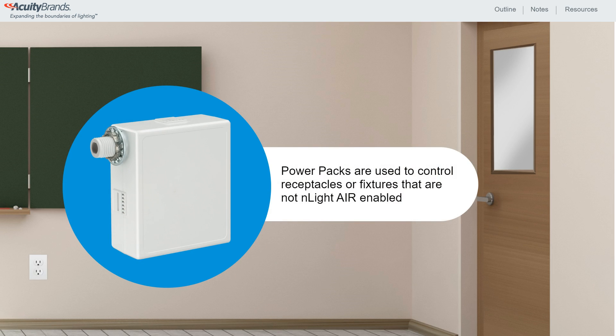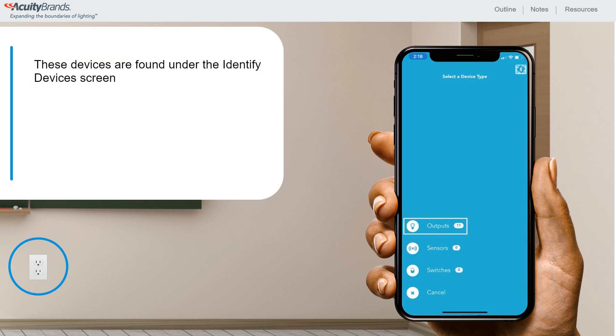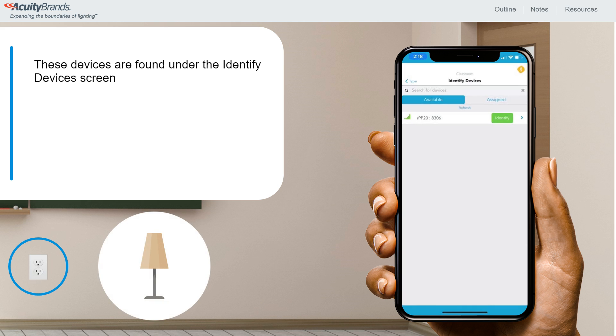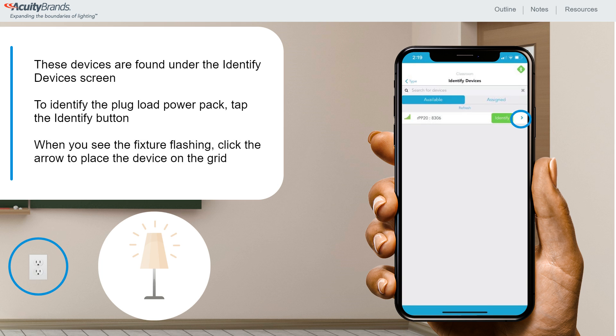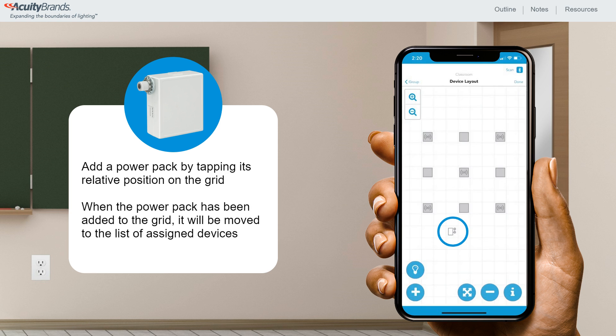For classrooms, several national energy codes require 50% of all receptacles be automatically turned off by an occupancy sensor within 20 minutes of all occupants leaving the space. In nLight Air, power packs, or RPP20s, are used to control both receptacles and other light fixtures that aren't already nLight Air enabled. Similar to enabled fixtures, they can be found under the outputs on the Identify Devices screen. You'll want to plug in a temporary light source into a controlled receptacle to test. To identify the power pack, tap the Identify button and watch the temporary light plugged into the receptacle. Once you see the fixture flashing, click the blue arrow to the right to place the device on the grid. To add the power pack to the grid, tap its relative position — place the device where it is actually installed above the ceiling, not where the device it's controlling resides. Once the power pack has been added to the grid, it will no longer appear in the list of available devices; it will be added to the list of assigned devices.